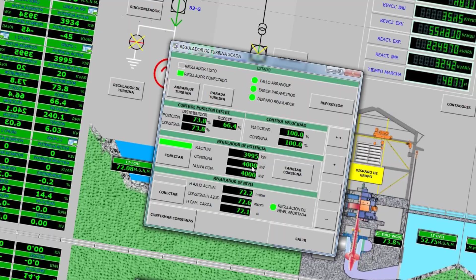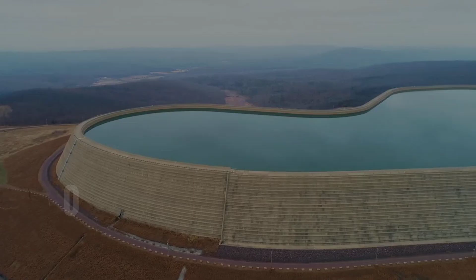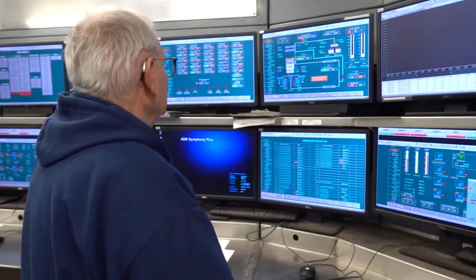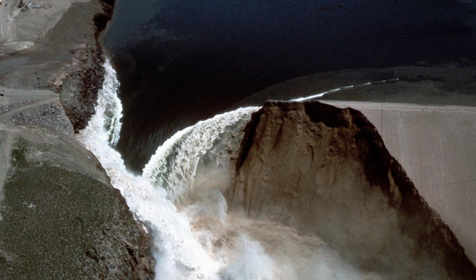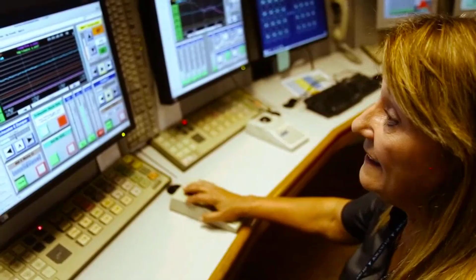Instead of shutting down the plant or physically repairing the sensor anchors, management chose a software solution. They reprogrammed the control system to stop the pumps when the sensors indicated the reservoir was 2 feet lower than the usual cutoff. This set point offset was a workaround, not a fix. Internal notes and maintenance logs reviewed by investigators show a pattern: known defects addressed with temporary measures, while the plant continued to operate at the edge of its limits. The real water level and the numbers on the screen were drifting further apart, but trust in the automated system remained. The vulnerability was now baked into daily operations, awaiting the next routine fill cycle.